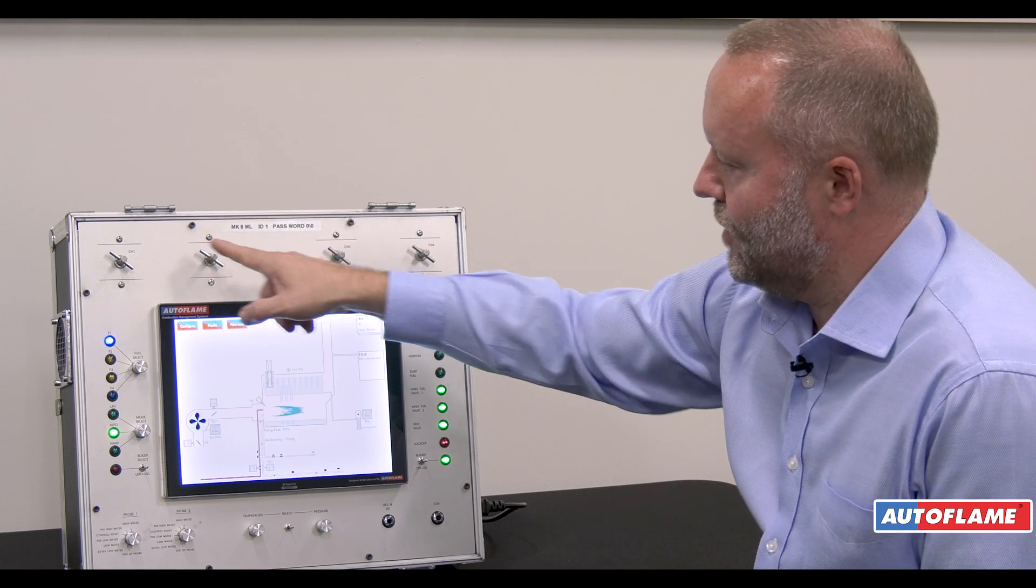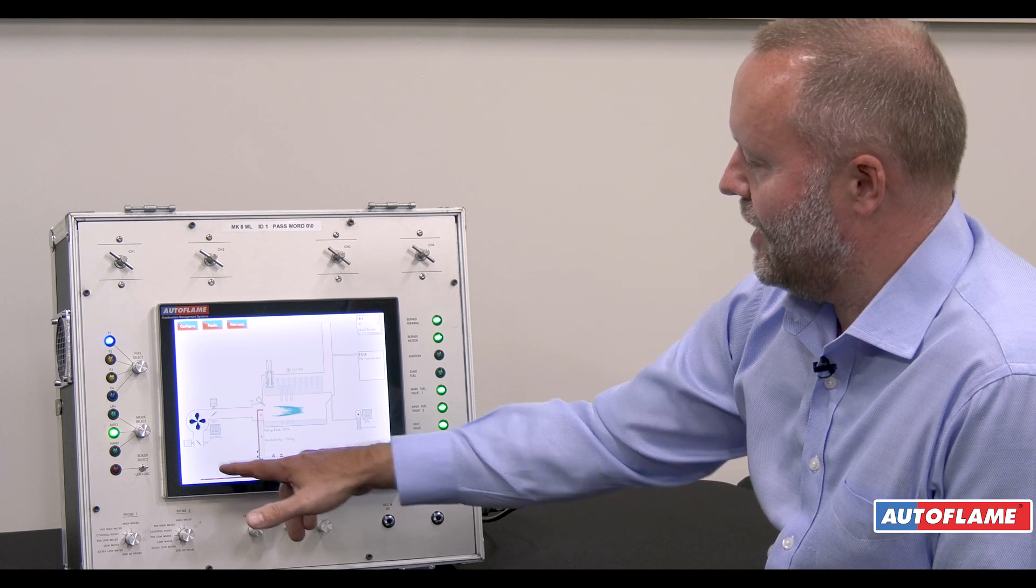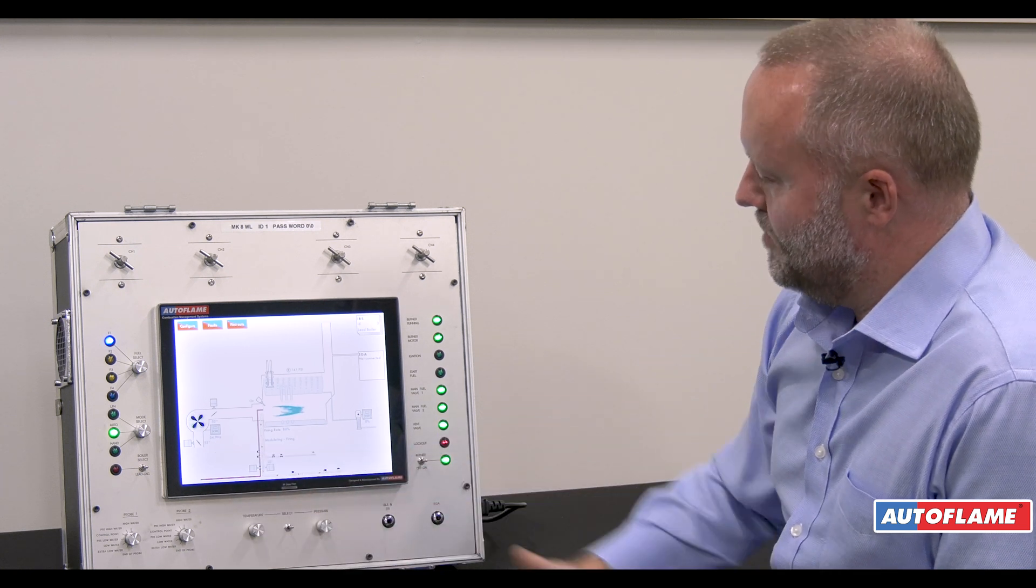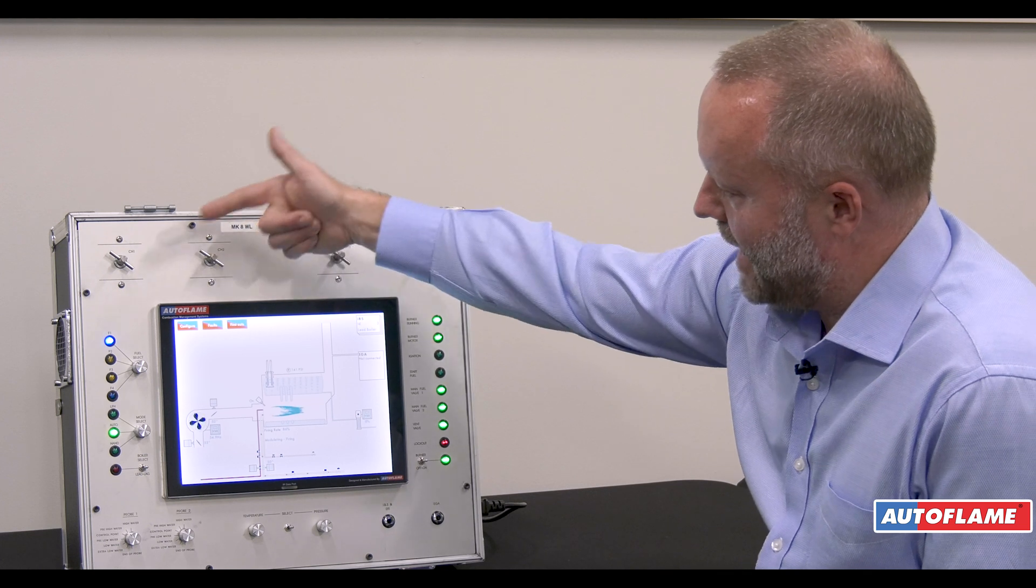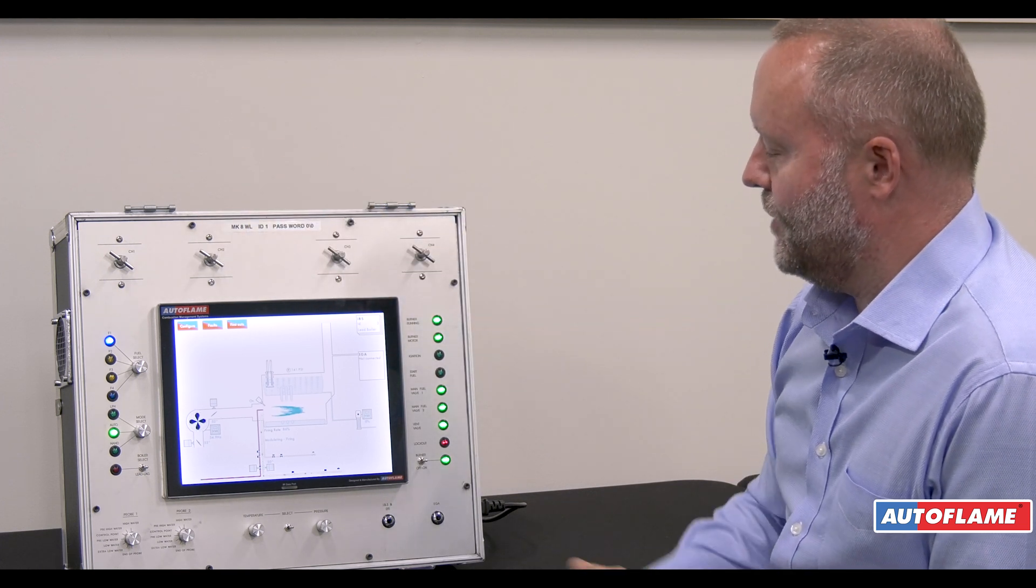So we'd commission the fuel air ratio based on the volume or mass flow of air and fuel, but if they failed we'd revert back to the normal parallel positioning control, meaning we have a full backup.